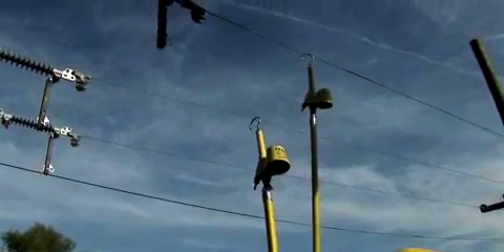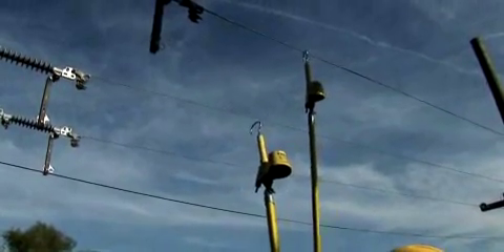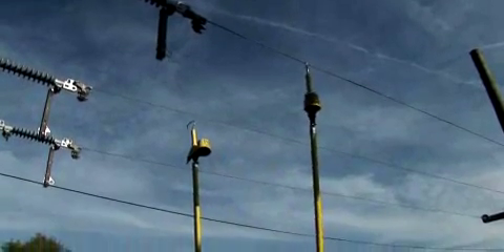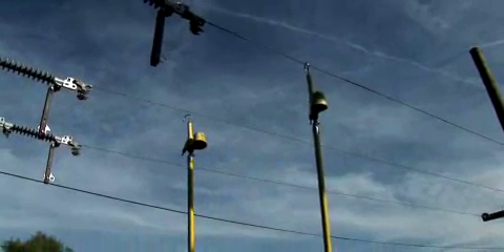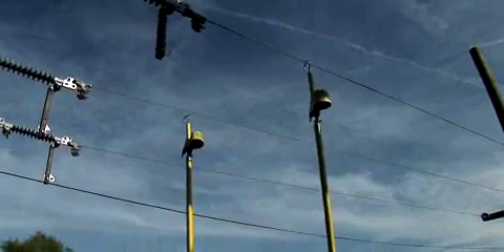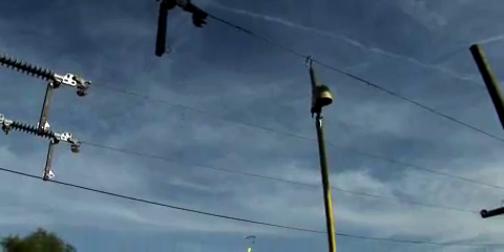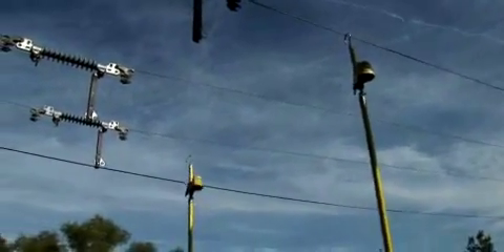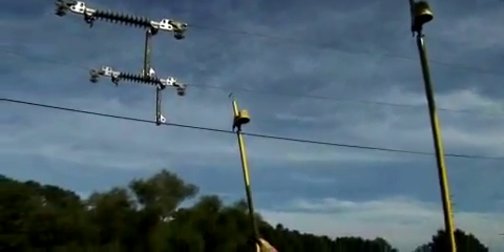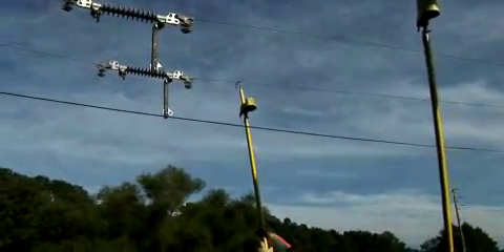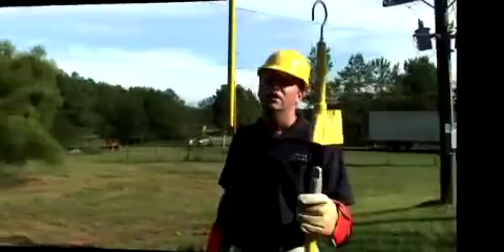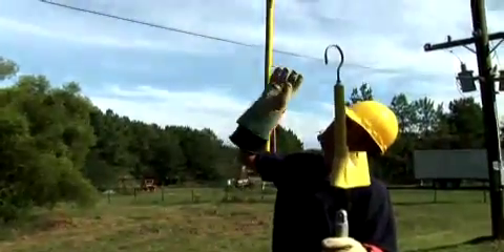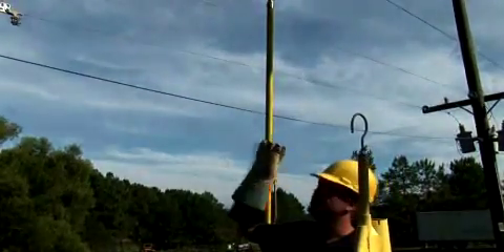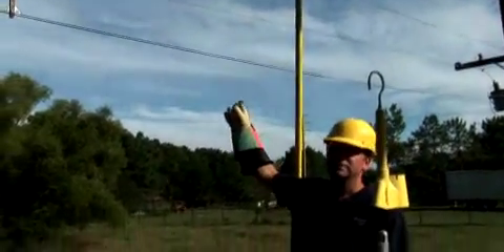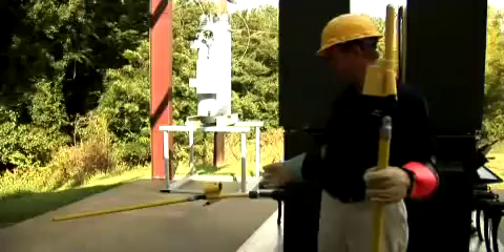So if I want to phase sequence this side of the switches and my reference probe is on that phase, I can place my meter probe here. I get a blue light, 126 degrees, and a red light, 238 degrees. Okay, so that tells me that my phase sequence is from the outer phase to the middle phase to the far phase.